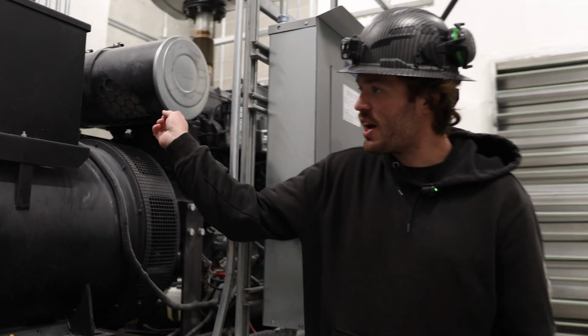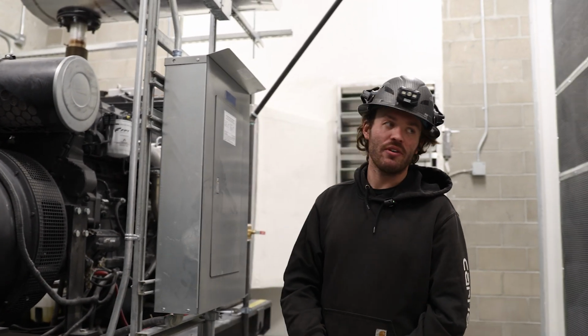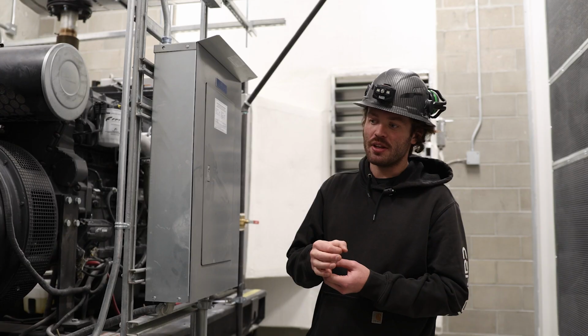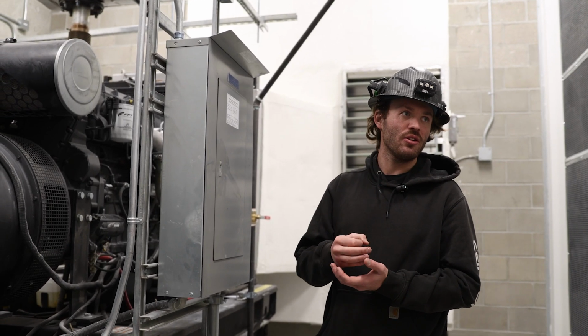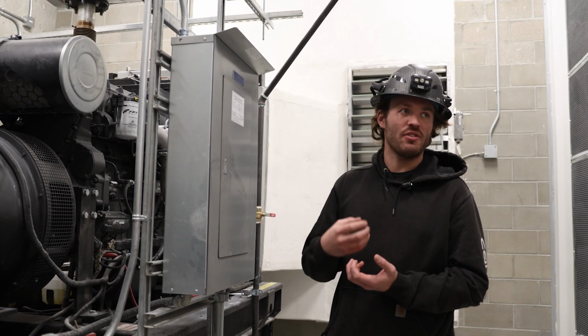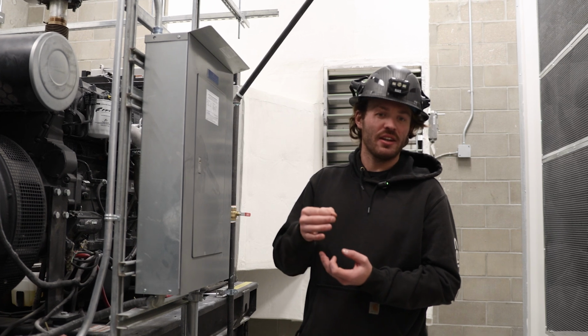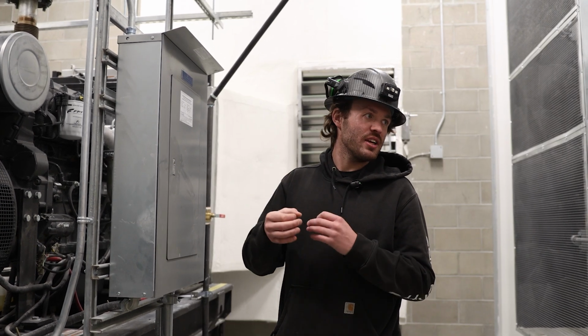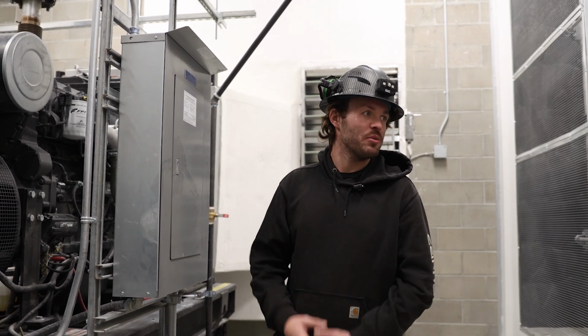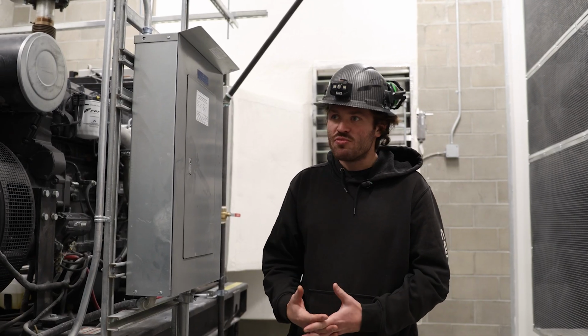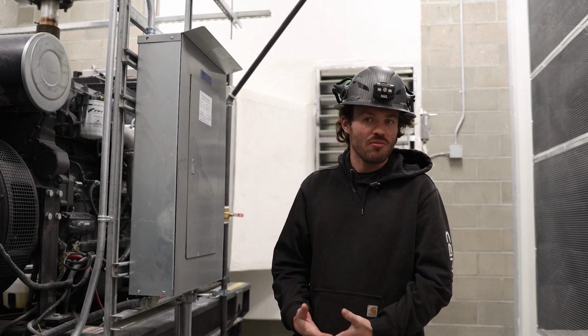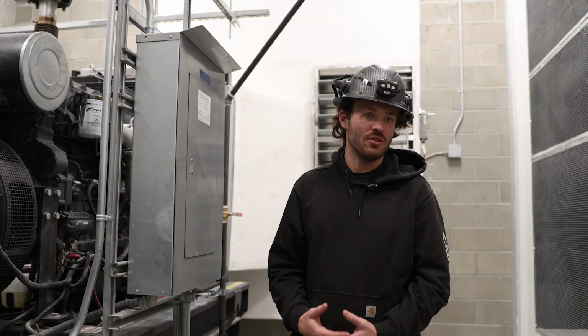On the opposite side, we have an indicator for it, a vacuum indicator. It's a little, I'll show it on the other side, but it's a little yellow line. Once the air filter becomes obstructed and dirty, it'll end up sucking that indicator up, and once it gets into a red zone, that's when it's due to replace the air filter. Once again, generally air filters have long service lives on generators just due to low run hours.